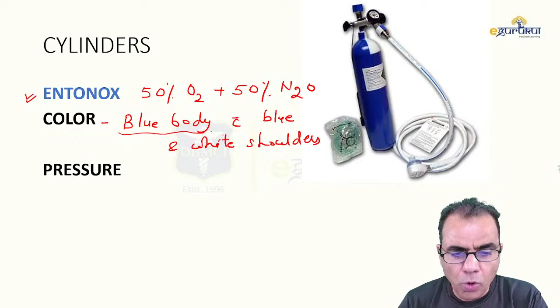Will it exhibit the pressure of nitrous oxide or will it exhibit the pressure of oxygen? Which is higher? Oxygen. So obviously the pressure will be 2000 pounds per square inch. So any gas combination carrying oxygen will exhibit the pressure of oxygen that we have seen. Entonox carries the pressure of oxygen, 2000. Similarly, air also has oxygen, so it also carries the pressure of oxygen.